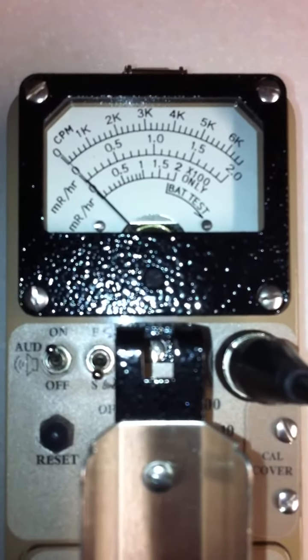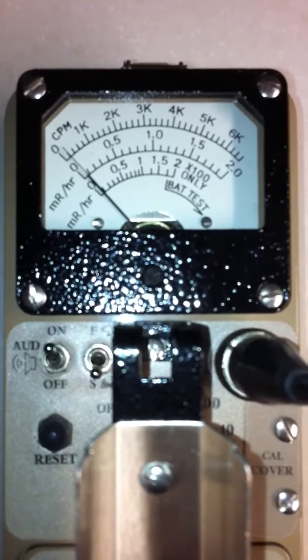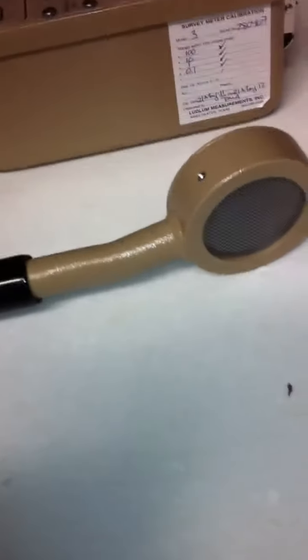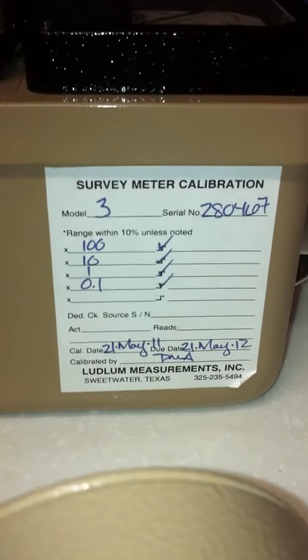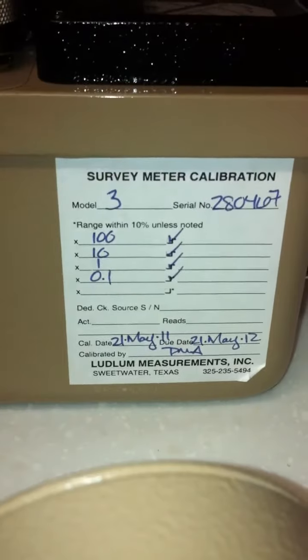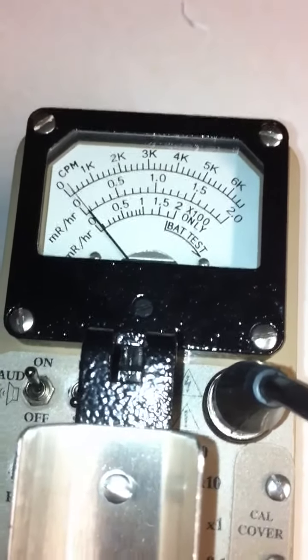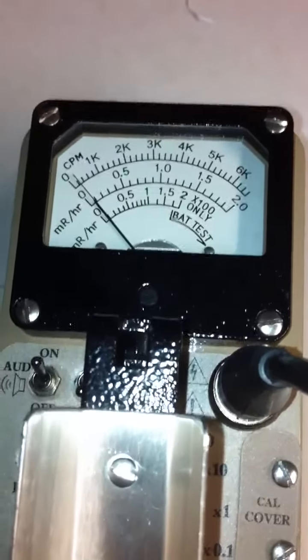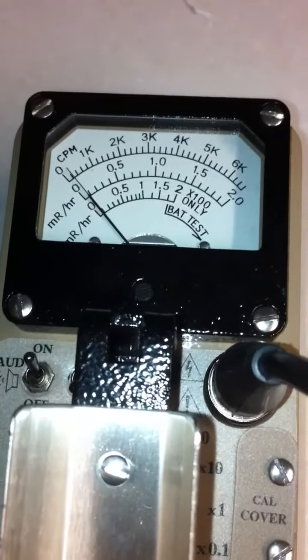See, I have barely anything. It comes in spurts for some strange reason. This is just the probe sitting sideways, this little pancake probe. This meter was just calibrated by Ludlum May 21st, 2011. So your background is about 20, 30 counts per minute.